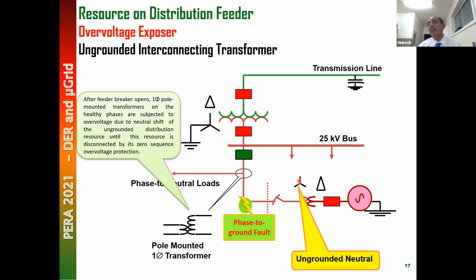You will also need a different type of protection, which we call zero sequence overvoltage protection. We also use zero sequence overvoltage protection in transmission lines, but it cannot operate instantaneously because it does not coordinate. It always has to be slow, with a time delay. It has to have 15 cycles of time delay or even longer, and that time is too long: the transformer, subjected to overvoltage, could get damaged. Sometimes the time has to be longer than 15 cycles, depending on the clearing time here. It could be much, much longer, could be seconds, and could damage this transformer.